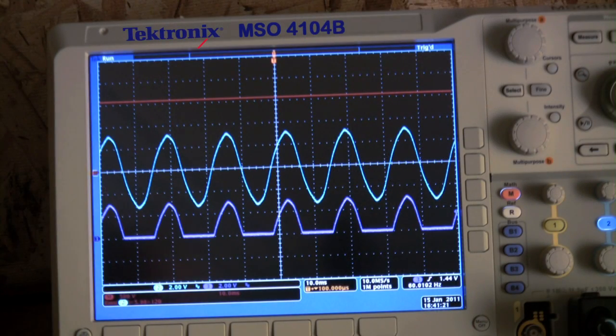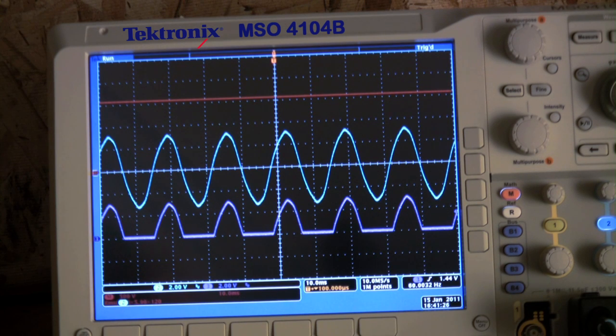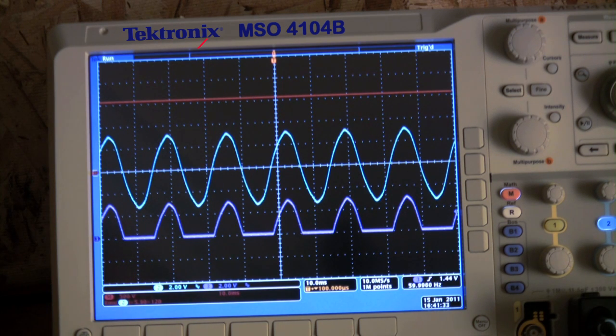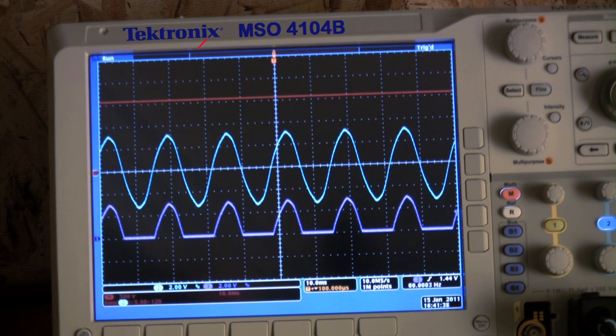The center trace is the current waveform from the current probe. You can easily see the harmonic distortion caused by the load, which is my shop heater that I'm using as a test device. The lower trace is one side of the precision rectifier. There's another side which rectifies the negative swing. The two sides are added together and averaged to DC to go to the data acquisition system.